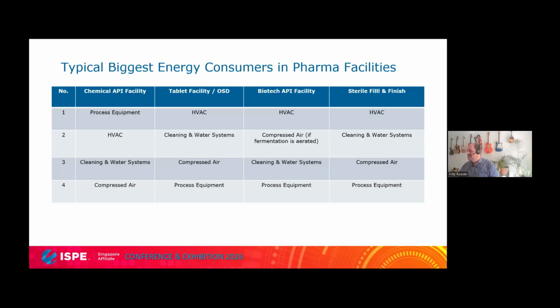There's so much you can do. For example, in a tablet facility, you don't need 20 air changes like it was written 20 years ago in the FDA aseptic guide. They wrote that 20 is typically sufficient. Yes, it is sufficient, but 8 air changes per hour is also maybe sufficient, and this is a huge saving, I can tell you.